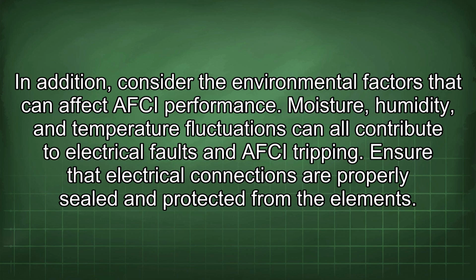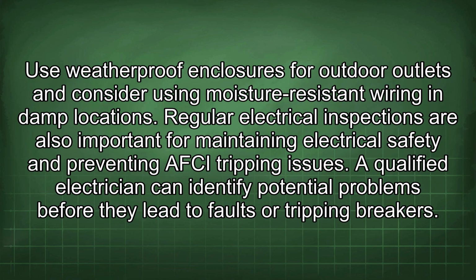Ensure that electrical connections are properly sealed and protected from the elements. Use weatherproof enclosures for outdoor outlets and consider using moisture-resistant wiring in damp locations. Regular electrical inspections are also important for maintaining electrical safety and preventing AFCI tripping issues. A qualified electrician can identify potential problems before they lead to faults or tripping breakers.